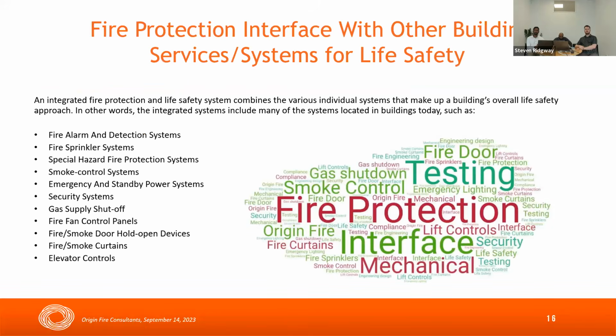Fire protection interfaces with other building services for the purpose of life safety. What does this mean? An integrated fire protection and life safety system combines the various individual systems that make up a building's overall fire safety approach. In other words, an integrated system includes many of the systems located in buildings today. There's a list there of a few types of systems typically found in buildings. It could be gas supply shutoff, fire fan control panels, fire and smoke curtains. Could be even interface with security doors.